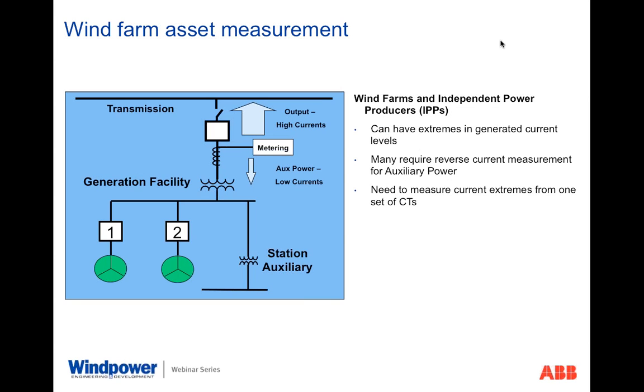One of the first things that we had problems with when we first looked at the development of wind farms was that there were extreme wide current swings in these applications. And the reason those swings existed is, of course, when you're generating power with a device that's 59.5% efficient, you're not always up and running 100% of the time. So you have varying current levels flowing to the transmission grid depending on the availability of your turbines. And so in this application, currents can adjust widely across the number of operating windmills, and it can also go all the way down to a very low level when nothing is rotating, and the transmission grid operator is actually sending power back into the facility for auxiliary power needs.